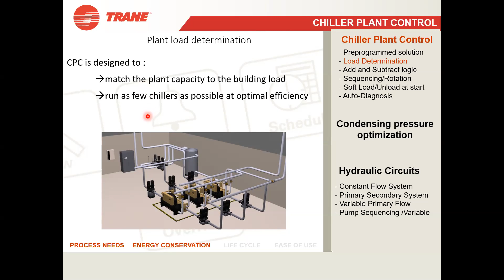I'll just go back to the previous slide to make you understand one more thing. Suppose this is my secondary side, and the load is on this side, the office where we are throwing the cold air. At 11 o'clock in the morning, that is full load. So the system senses that the full load is there, and this secondary pump will be running at its full load. Primary you cannot control; primary will always run at full load. If it is a big system, there will be a bypass line. All those things I will describe afterwards. Chillers will also run at full load one after another, and the cooling tower will also run at full load.